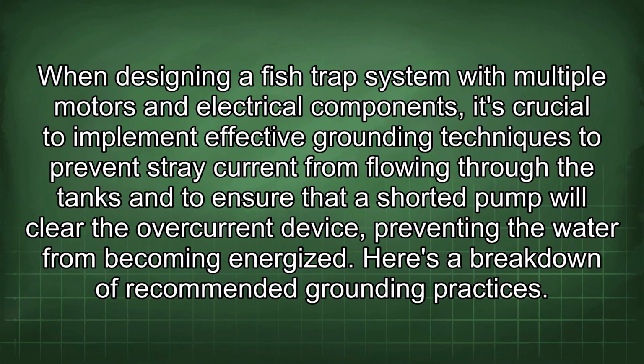When designing a fish trap system with multiple motors and electrical components, it's crucial to implement effective grounding techniques to prevent stray current from flowing through the tanks and to ensure that a shorted pump will clear the overcurrent device, preventing the water from becoming energized. Here's a breakdown of recommended grounding practices.